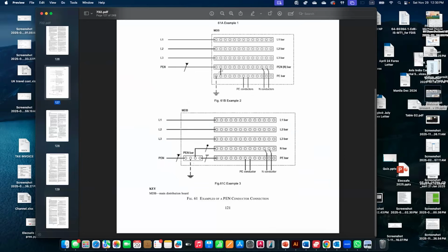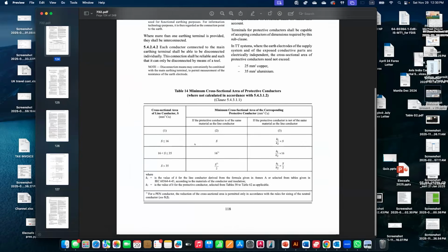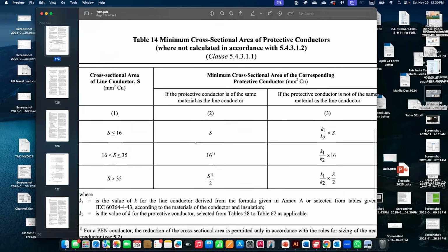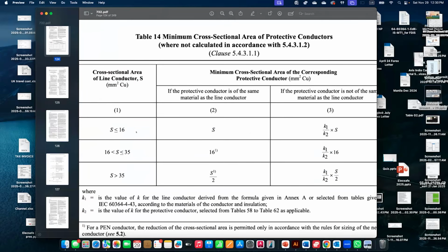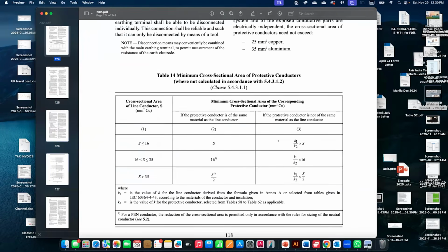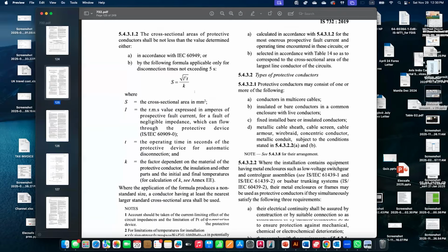If you are having a protective conductor, there are two ways of sizing it in general. One way is you size it according to the live conductor. So if you have up to 16 square mm live conductor, same material, use the same size. Different material, there's a K factor. If it is between 16 and 35, you use only 16 square mm. If it is greater than 35, you use half the size. And of course, in different material, there's a factor. Alternatively, you can size it according to the short circuit current that it is expected to carry. So there are two ways of doing it.